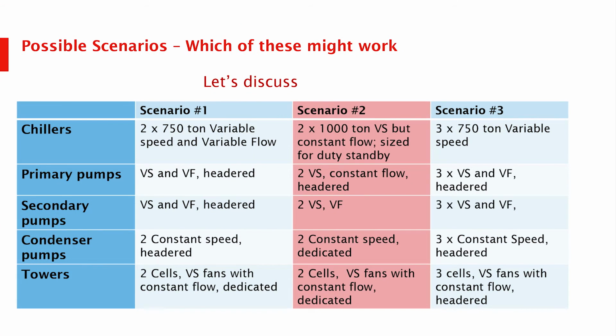And you can't trust the baseline data from the BAS. It doesn't mean it's going to be wrong, but it might not be right. That flow meter might not have been calibrated for 15 years. And so you'll get data that you think is the building load, and it's nothing like that at all. Right? Or the DP sensor might not have worked properly for 9 years, and people can't find it anymore. So when you get data that you want to use in the baseline, make sure that you have something to calibrate it with.